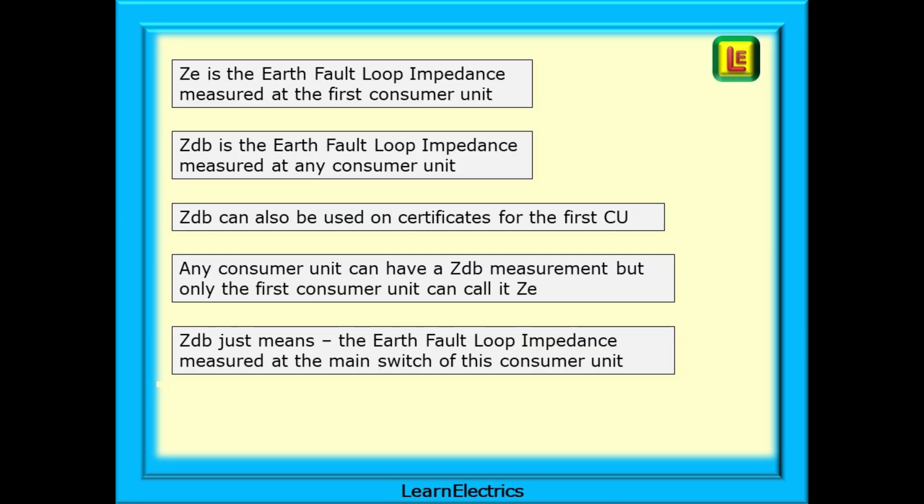A recap on this. ZE is the earth fault loop impedance measured at the first consumer unit. ZDB is the earth fault loop impedance measured at any consumer unit. So ZDB could also be used on certificates for the first consumer unit. Any consumer unit can have a ZDB measurement, but only the first consumer unit can call it ZE.